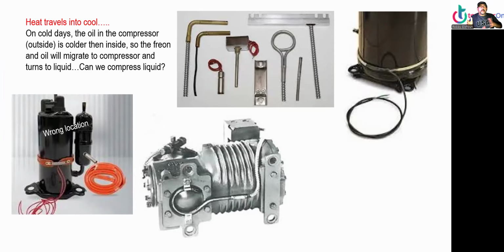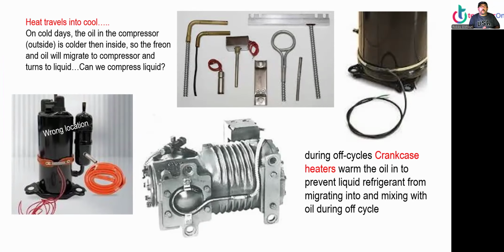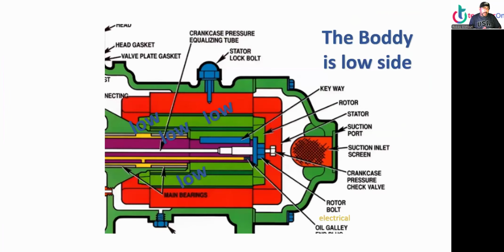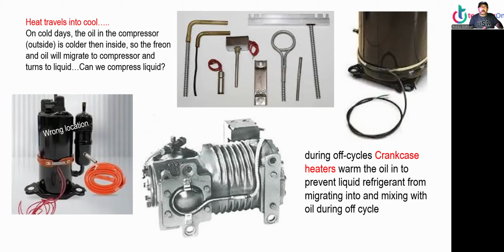Heat travels into cool. You've got to remember, on cold days, the oil in the compressor outside is colder than inside. So the freon and oil will migrate to the compressor and turn to liquid. Can we compress liquid? I don't think so. That's why we need a crankcase heater. During the off-cycle, the crankcase heater warms the oil to prevent liquid refrigerant from migrating and mixing with the oil. That's why it's important, before you turn on the AC the first time, to plug it in for at least 24 hours without turning it on so it can warm up the oil.